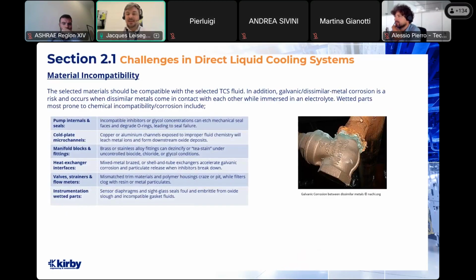So firstly, material incompatibility. The selected materials of the technology cooling system have to be compatible with the selected fluid that's being used, whether that fluid is water, a glycol-based coolant, or a dielectric fluid. All the materials selected need to be compatible. In addition, galvanic or dissimilar metal corrosion is a risk. This occurs when dissimilar metals come into contact with each other while immersed in an electrolyte. Incompatible materials with a large difference in electrochemical potentials cause metal degradation within the system. This creates debris which can clog the cold channels in the cold plates and abrade surfaces. Corrosion can increase the risk of leaks, and suspended debris wears component surfaces.